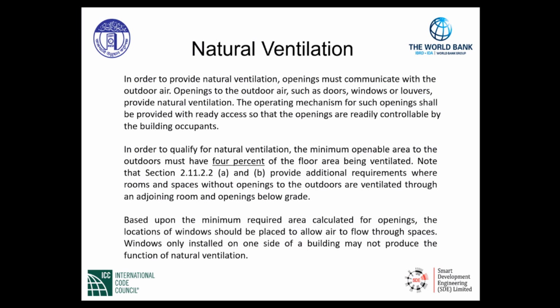Natural ventilation is given here. In order to provide natural ventilation, openings must communicate with the outdoor air. Openings to the outdoor air, such as doors, windows, or louvers, provide natural ventilation. In other words, we need openings to the exterior to draw in fresh air and properly ventilate the building. Not only draw in fresh air, but we hope that the air that's drawn into the building will somewhat disperse through the building and be exhausted out the same openings naturally.